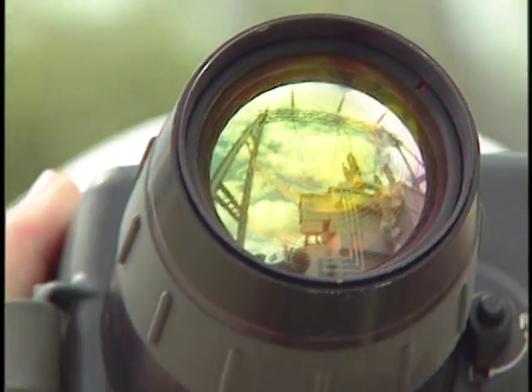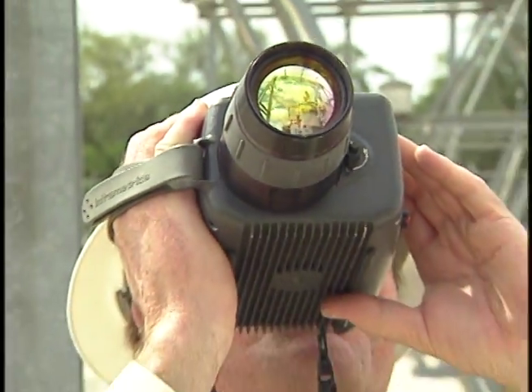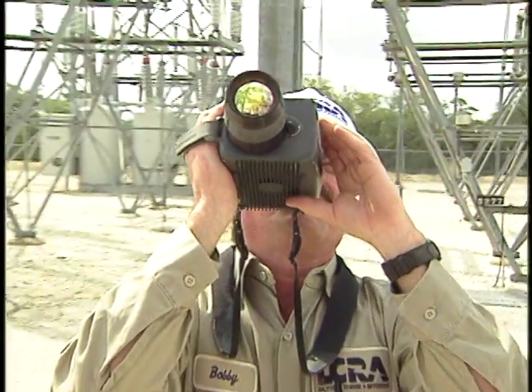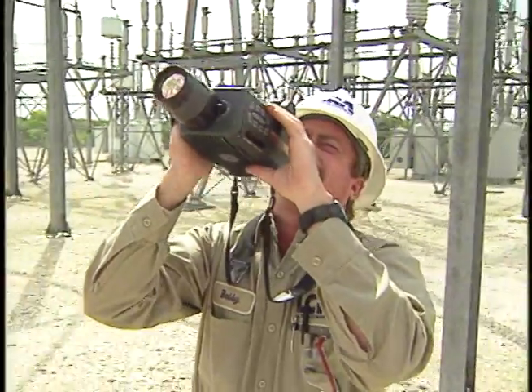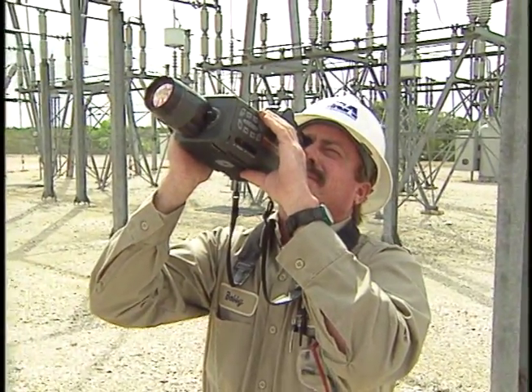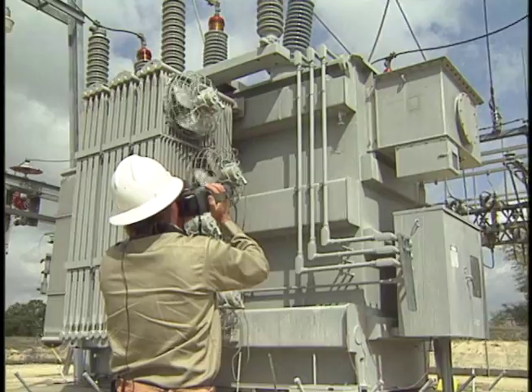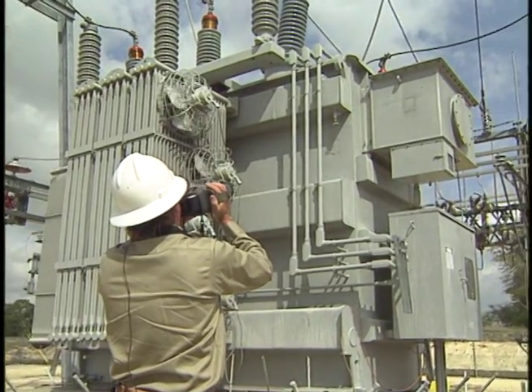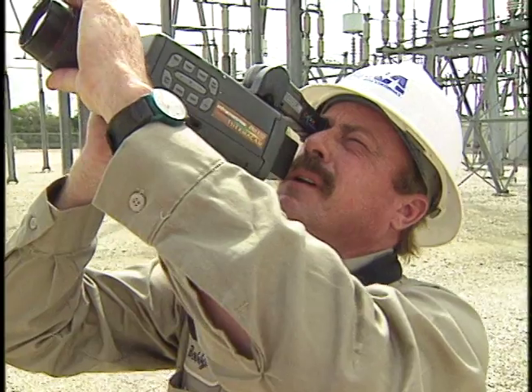This infrared camera is just one of the tools used by TENSCO's Diagnostic Services Group, who look and listen for potential problems, all while the substation equipment stays in service. The main thing we're doing is looking to minimize maintenance costs and minimize outages. If we can identify a problem, we can take corrective action to get it fixed or schedule it to be fixed before the untimely event of a power outage.